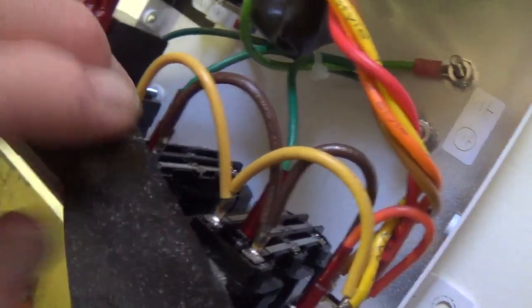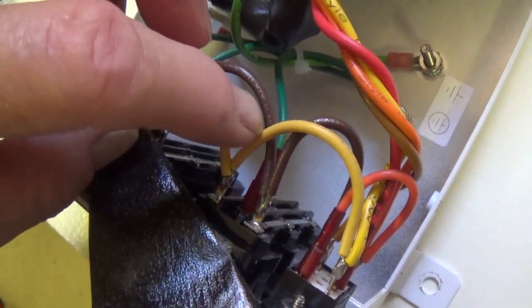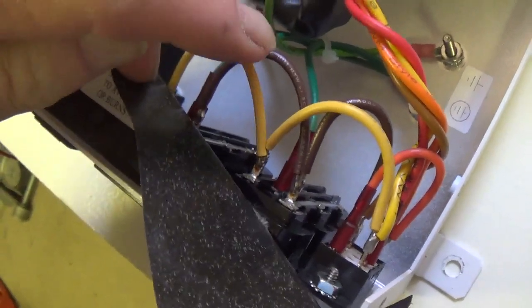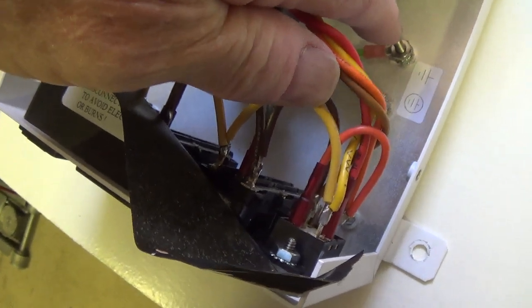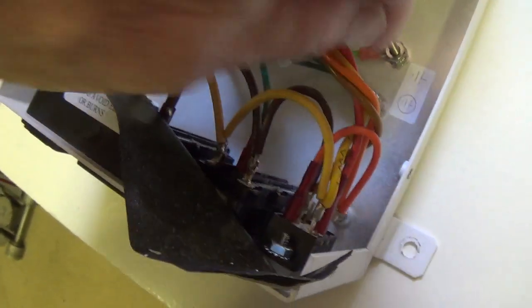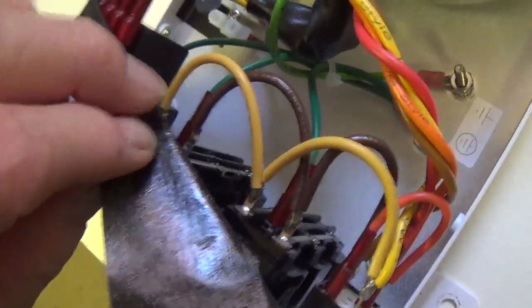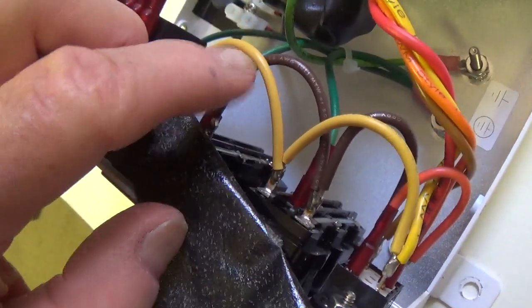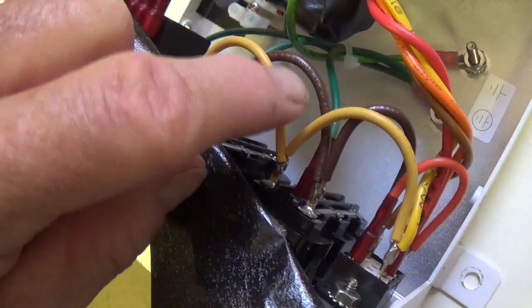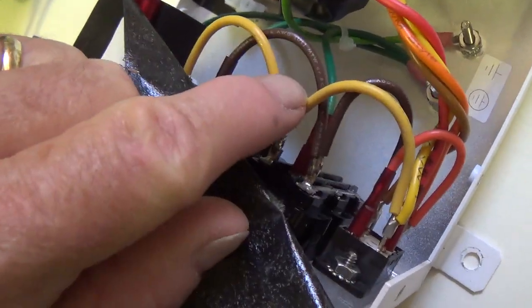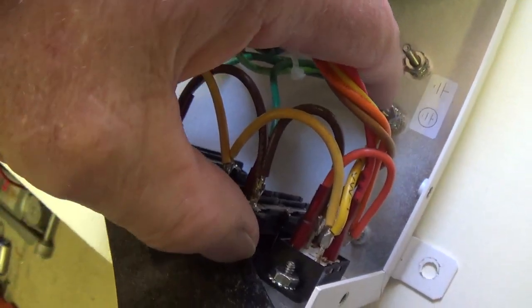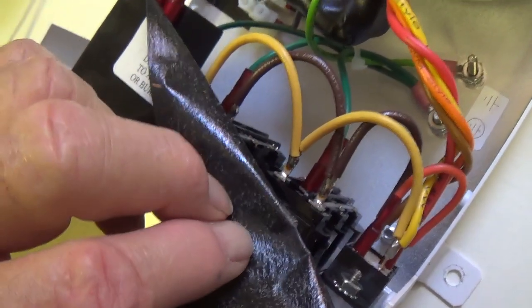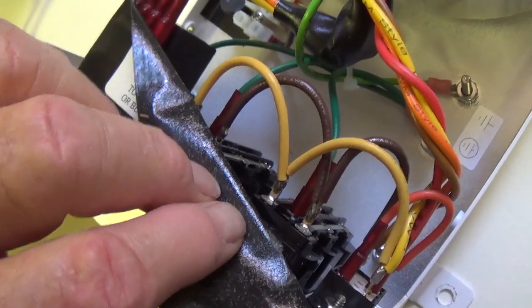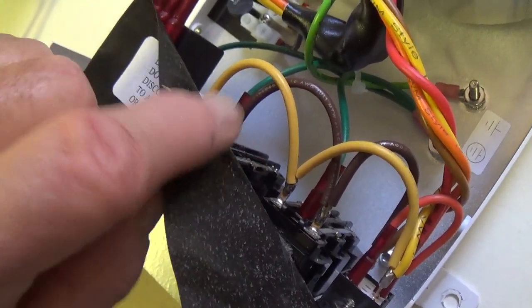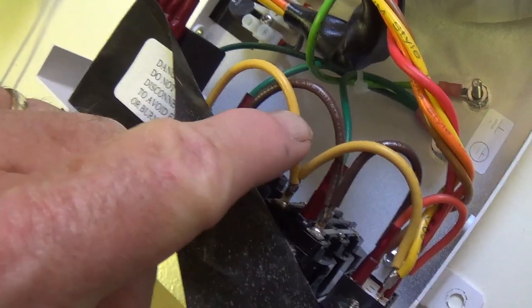Somewhere in your medical grade isolation transformer, there will be a connection between the neutral return and ground. If that exists, then remove it. You see that doesn't exist in this one. You want to make yours like this, with no ground connection between the neutral return and somewhere on the chassis where it'll be bolted down. Okay, so that's how you can salvage your medical grade isolation transformer and turn it into a tech grade one like this.